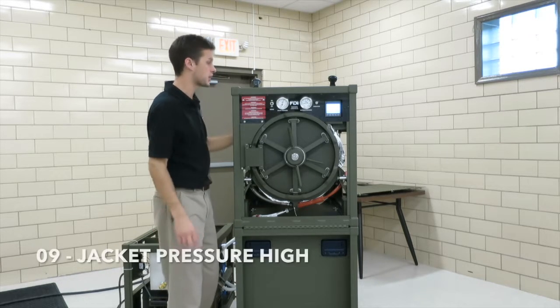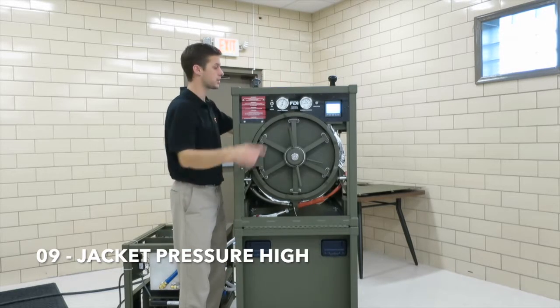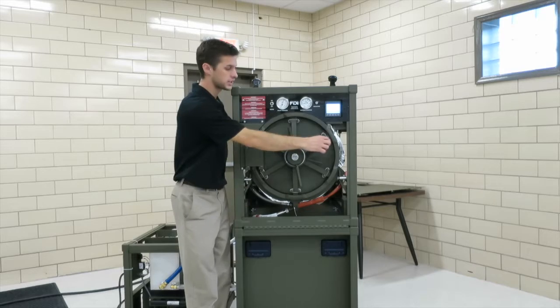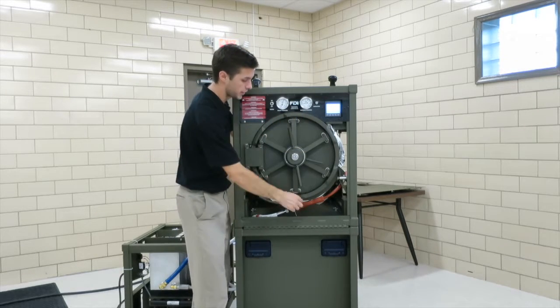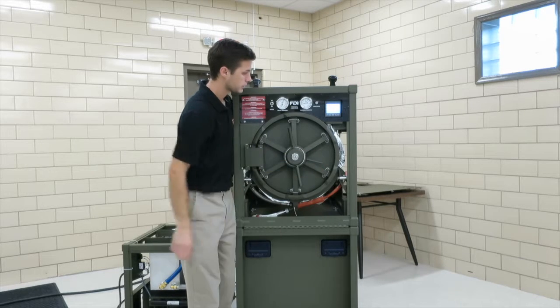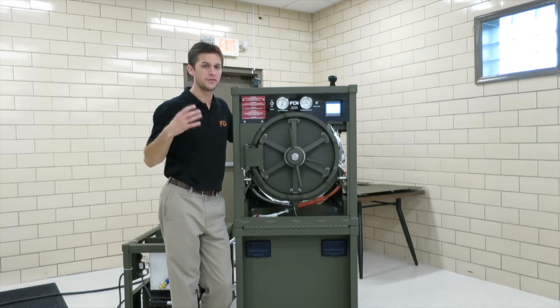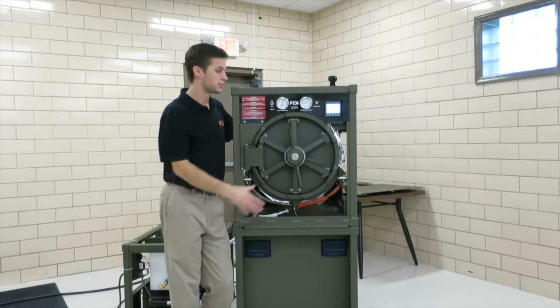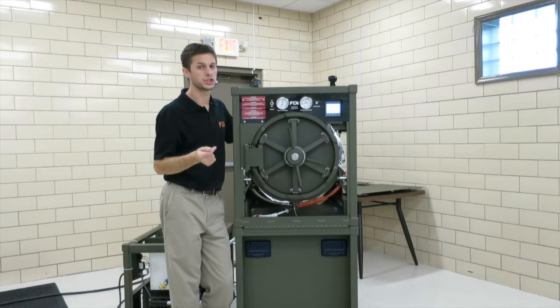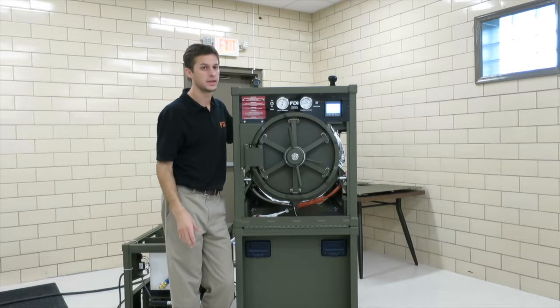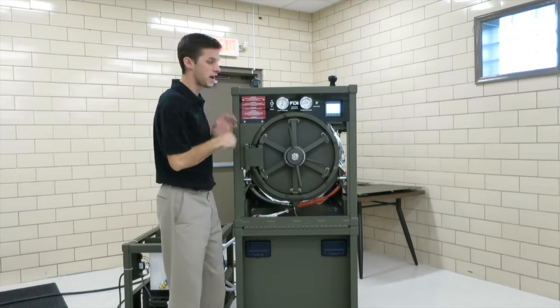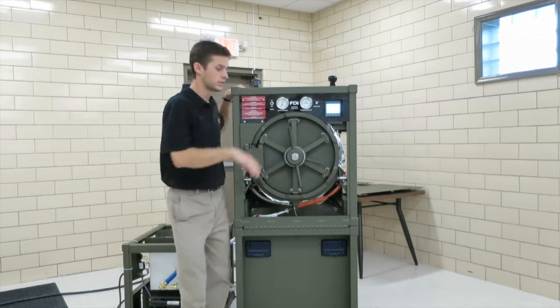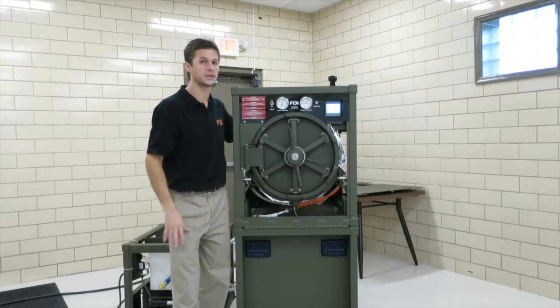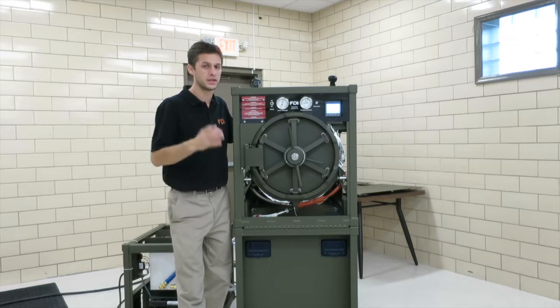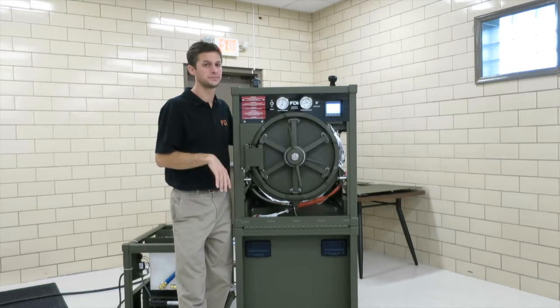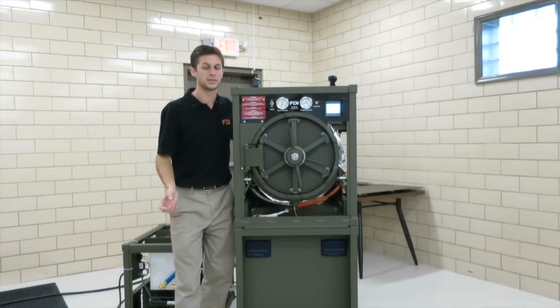So 09 jacket pressure high. Just like we have a chamber pressure transmitter, we have a jacket pressure transmitter that's measuring the pressure of the steam and water in the gap around the chamber. And if that gets too high, to protect the user, the whole system, it'll shut everything down. So if that jacket pressure gets high, same thing with the chamber pressure gets high, it'll close all the valves, turn off the heaters, and it'll just sit there. You can just turn it off. We want to shut everything down and not try to open valves and vent and fix things, because just to protect the user, to shut everything down, that'll protect you.